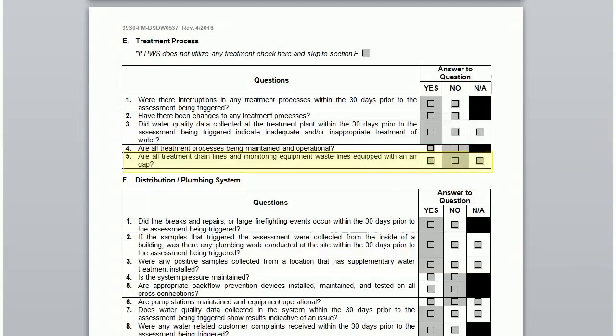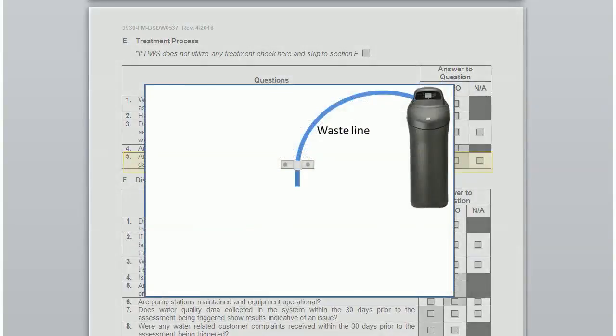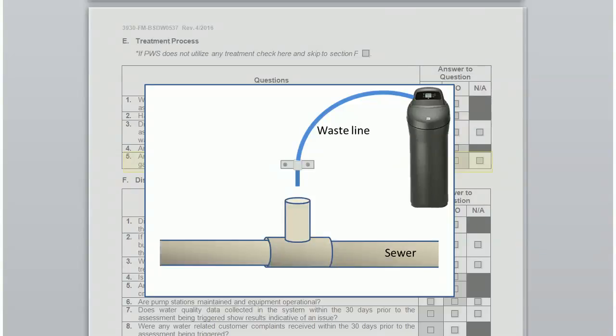The last question in this section asks: are all treatment drain lines and monitoring equipment waste lines equipped with an air gap? This is very important and often not correctly set up. For example, if you have a softener, there is a waste line for the backwash water. This line goes directly to the sanitary sewer. Where it connects to the sewer, there must be a space between the discharge line and the sewer pipe — this is called an air gap. The gap prevents water in the sewer from entering the softener discharge, which could otherwise end up in your drinking water system.